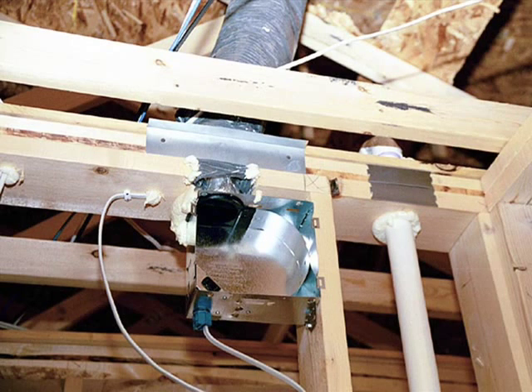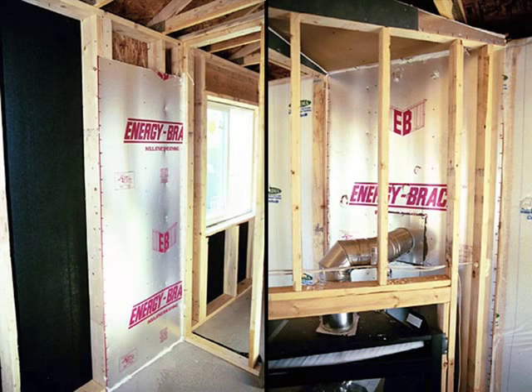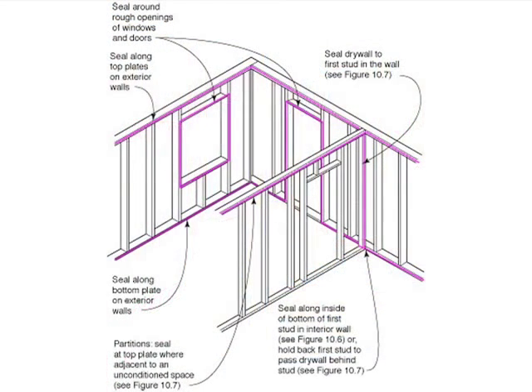All holes in the exterior wall assembly and holes between floors need to be sealed as well. Interior wall-to-exterior wall connections also present a challenge to maintaining the continuity of the insulation as well as the airflow retarder. Drywall should be sealed around rough openings of windows and doors, at top and bottom plates of exterior walls, and where interior walls meet exterior walls.